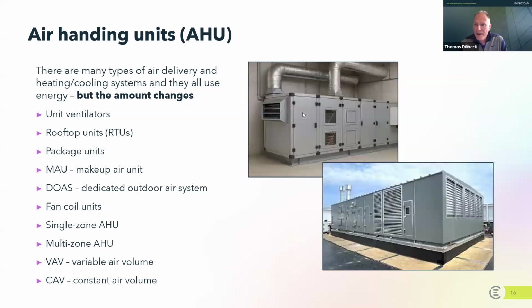If you take that same air handling unit and plop it on the roof, it graduates into the category of a rooftop unit, or RTU. So air handling units can be inside the building, as this picture shows, or on the building. But what they typically do is ventilate—pulling air from outside, heating or cooling it, and pushing it into the building.